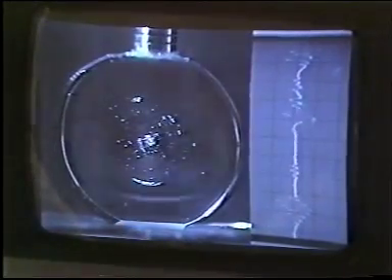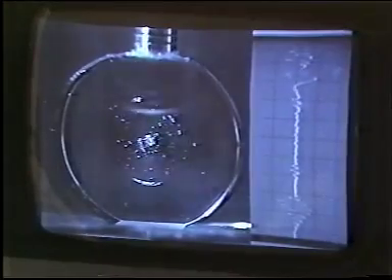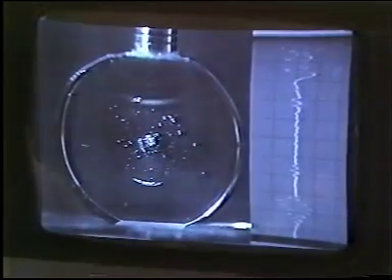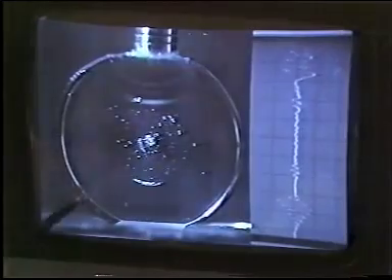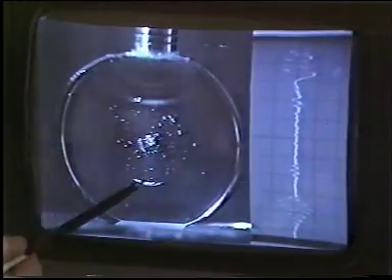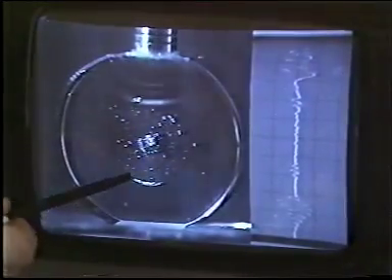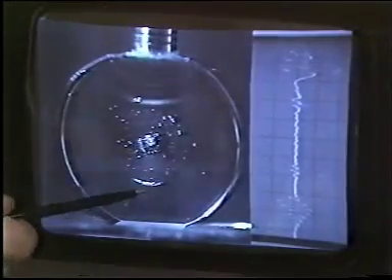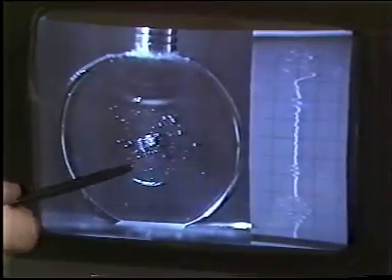Okay, well, I'll bring that back to there again. Now, what about the bubbles that we talked about earlier on? You can see them in the block, in fact, there. What I need to do is to move the transducer, and we should be able to see signals coming back from these defects. So I'll do that now.